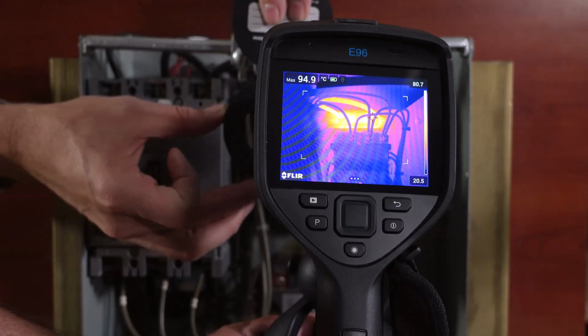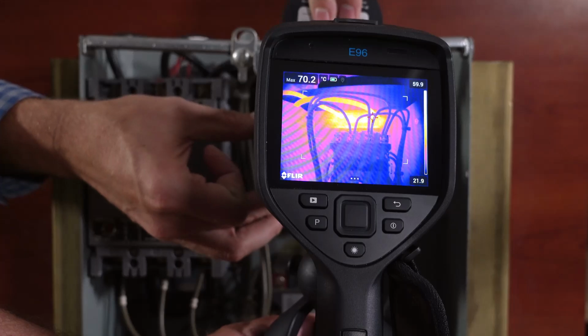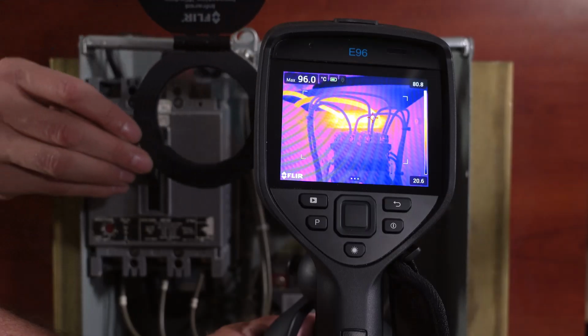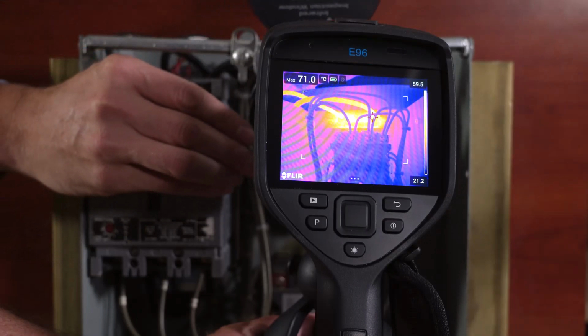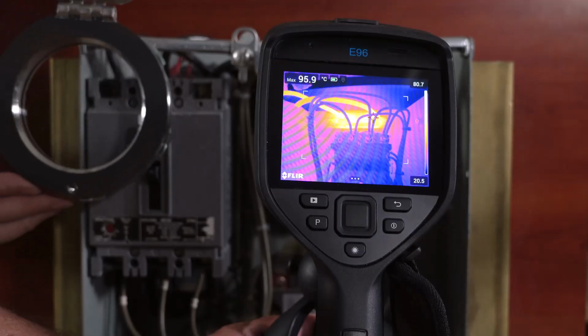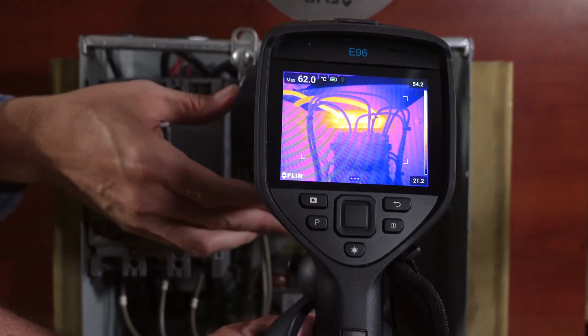The 24 degree lens provides a relatively narrow field of view. If there are a lot of components inside, it may be difficult to see them all. The 42 degree lens is better, with an image that is almost double the width of the 24 degree. The 80 degree lens is the best for this application, and as you can see here, you get a really wide field of view, double that of the 42 degree lens and almost 4 times the width of the 24 degree.